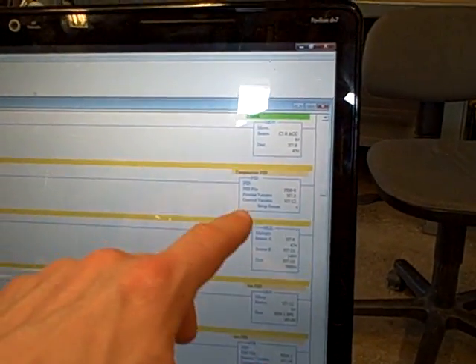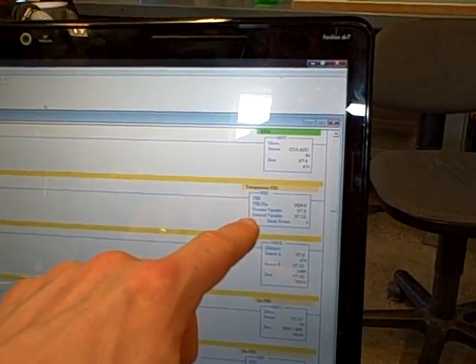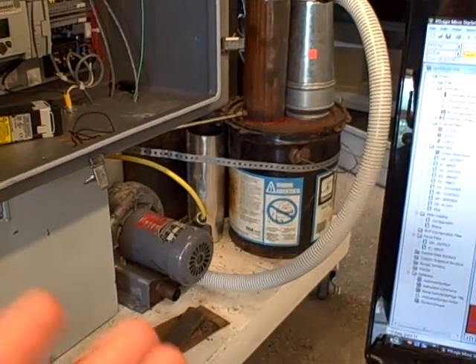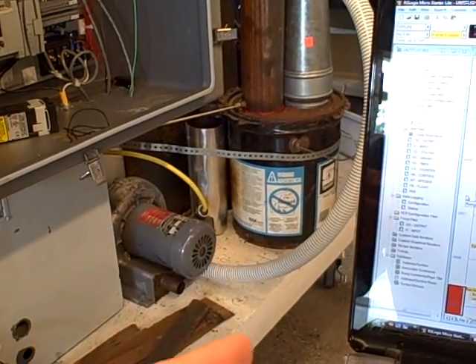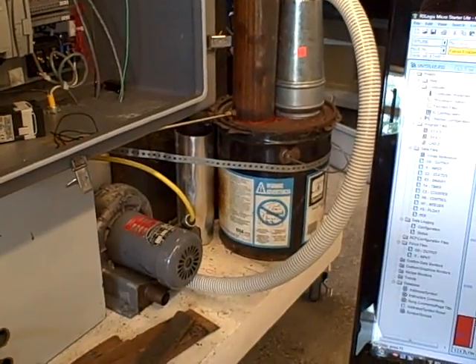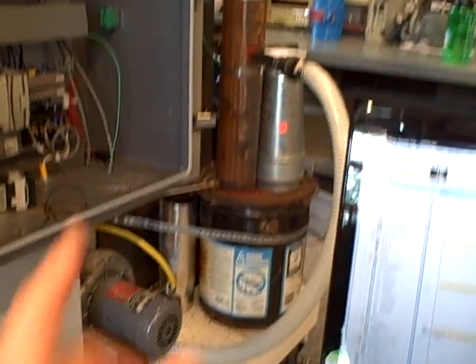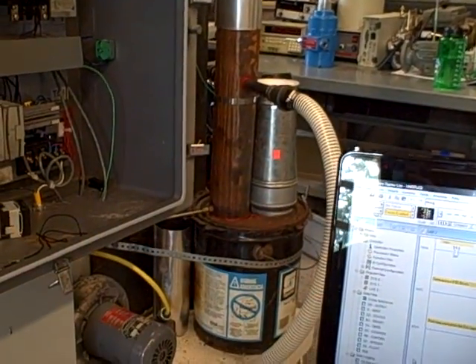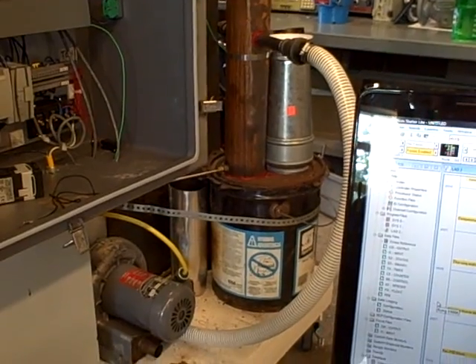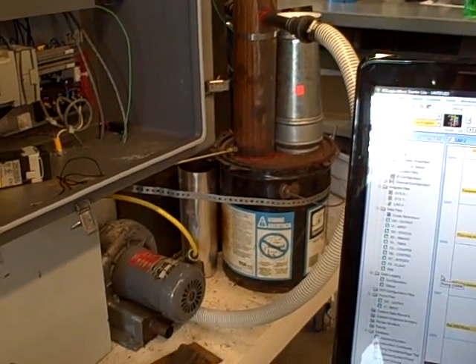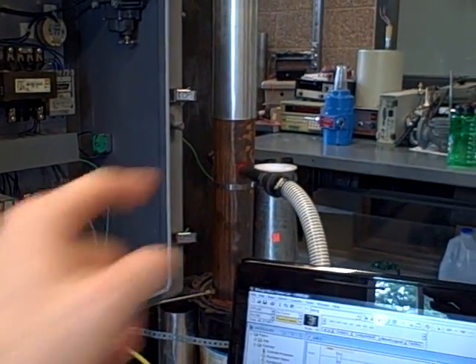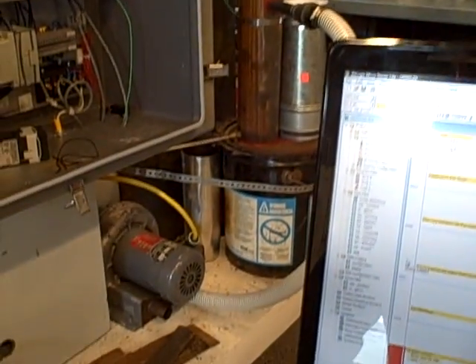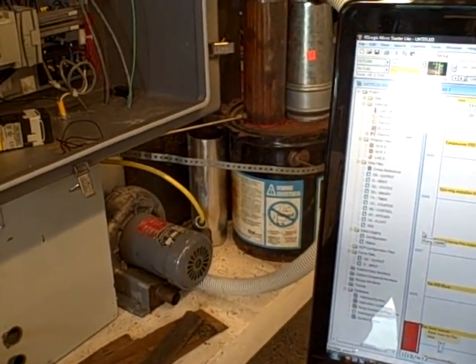The temperature PID instruction looks only at the furnace temperature and decides whether more or less air flow is needed. It then sends a signal which becomes a set point to the air flow controller. The air flow controller looks at the spinning turbine and asks whether it's flowing as fast as desired. If it isn't, it changes the motor speed to induce a different amount of draft in the stack to get air flow where we want it. And that's our cascade control system.